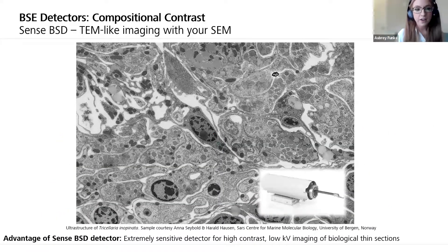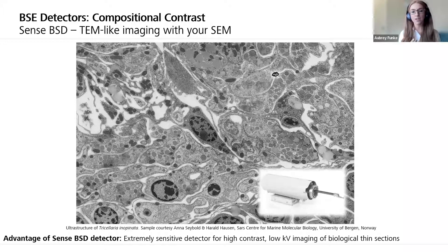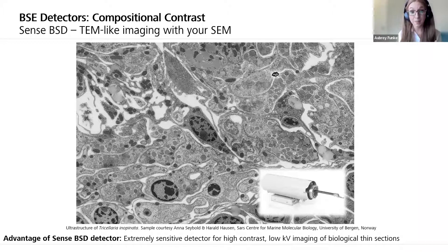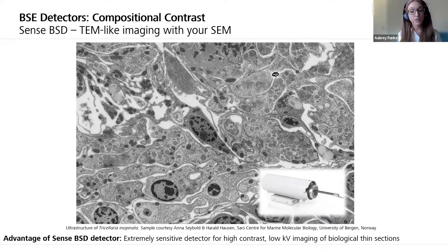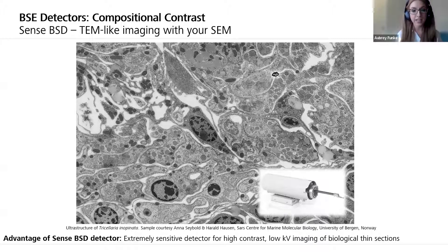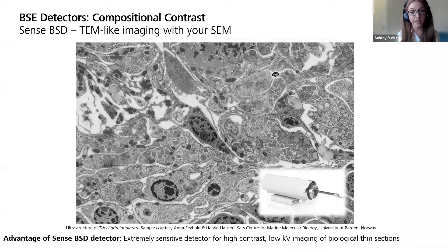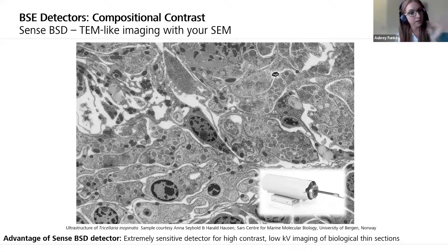Another type of backscattered electron detector is the Sense BSD, which gives us that TEM-like image with our SEM. EM technology has advanced such that getting these types of images has become possible with the SEM alone. The Sense BSD detector is specially designed for imaging ultra-structure because it has a new type of diode that is extremely sensitive — we can detect very small numbers of backscattered electrons and convert those signals into a high-contrast image. This is really important for life science samples that might not have as much backscattered electron signal.